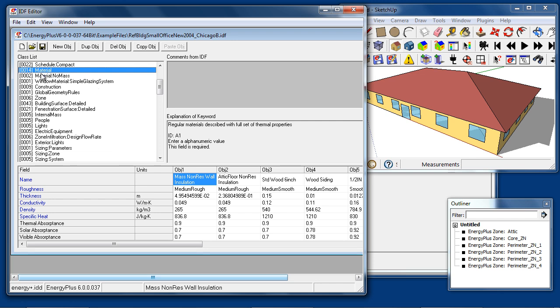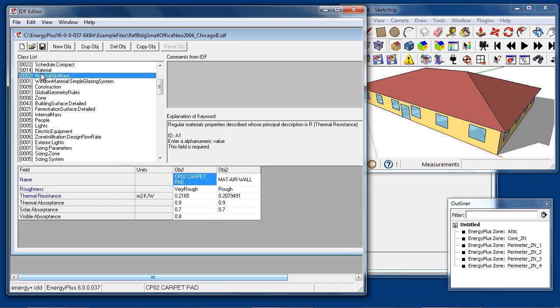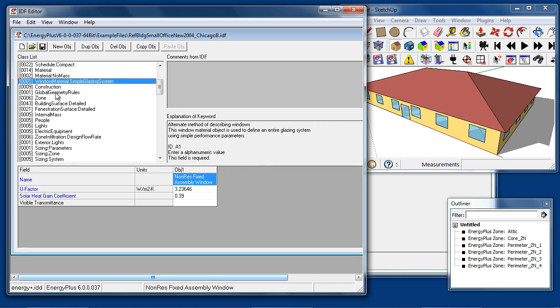There are some material no-mass objects in this to represent simple insulation or carpet layers. Window material simple glazing system represents a simple way of describing glass which takes just a U-factor, solar heat gain coefficient, and visible transmittance. The model will internally turn that into physical layers of glass and gas.